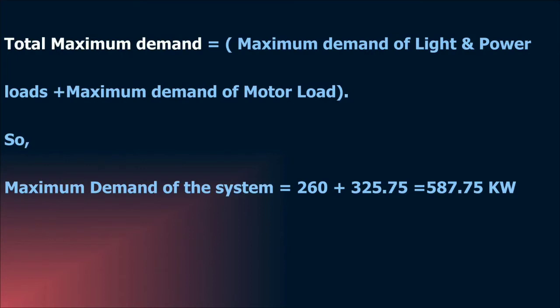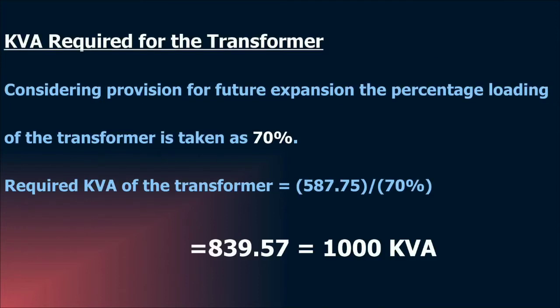The maximum demand of the system will be the sum of the maximum demand of the motor load and the maximum demand of the lighting and power load, which will be giving the value of 587.75 kilowatt. Now we are selecting the transformer rating by applying a percentage loading of 70% in consideration with the provision for future expansion. So after the calculations, the kVA required is arrived as 839.57 kVA. The nearest standard rating of the transformer is 1000 kVA, and so we are choosing 1000 kVA.